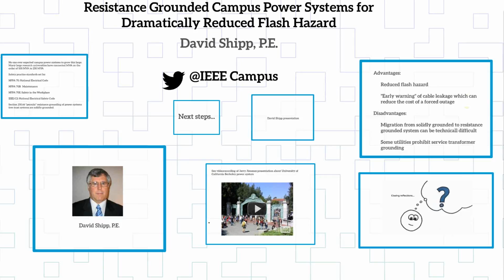Now, on the other hand, if I resistance ground it, I can't do high resistance at that level, it's too high a voltage, but I can do 400 amps, 600 amps, and if I can limit the ground fault current when I do get that fault to a few hundred amps, I allow enough amps to flow that I know where it is, I can get my protection to trip it off in 0.1, 0.2 seconds. You go find the fault, you replace 5 feet, splice 4 or 5 feet of cable at the fault point, and you're done. And you're back in service in a few hours at most.